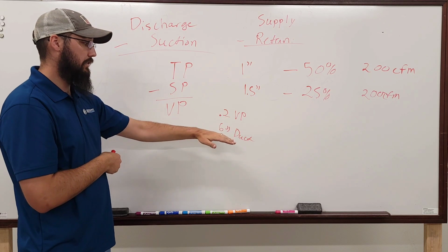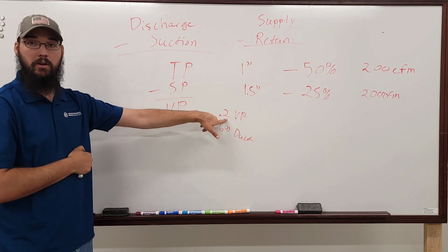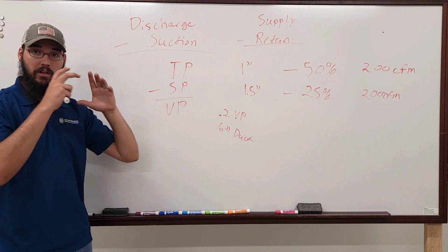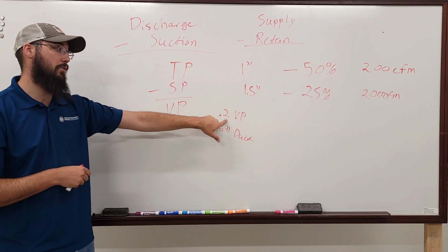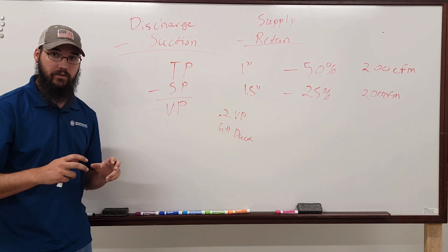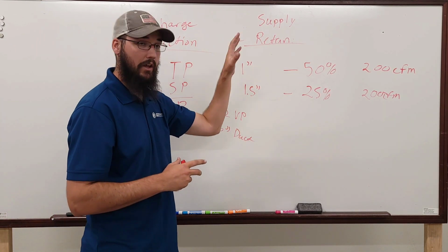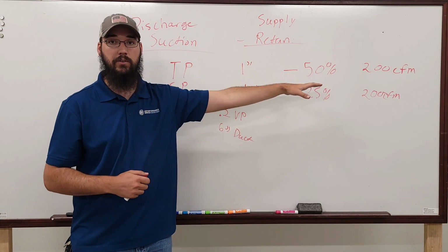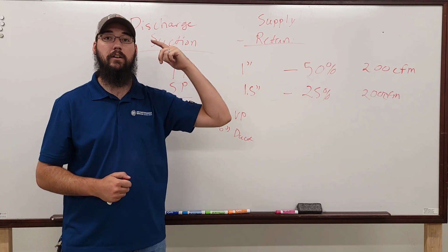Because again, that box, what it's trying to do is it just wants to maintain a 0.2. Like, that's all it sees. The box, the logic just sees, okay, I want a 0.2. Now, the graphics interpret the rest, and it spits out CFM and 50% and all this other stuff for us, because that's what we understand.